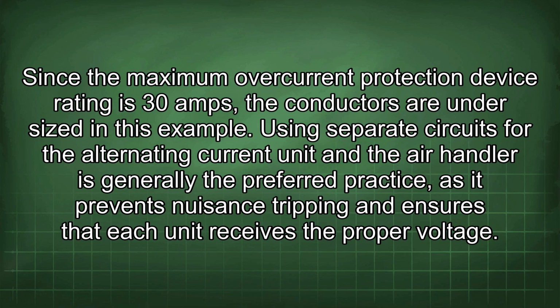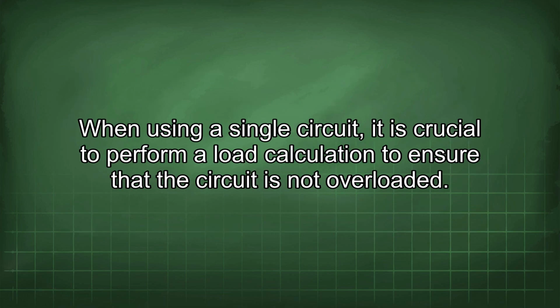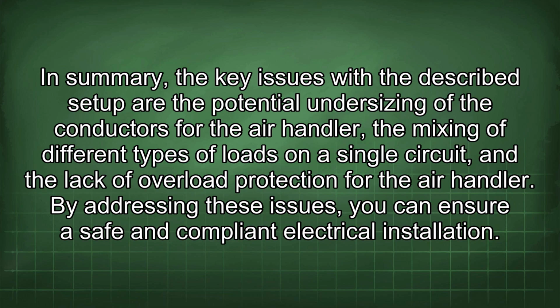Using separate circuits for the alternating current unit and the air handler is generally the preferred practice, as it prevents nuisance tripping and ensures that each unit receives the proper voltage. When using a single circuit, it is crucial to perform a load calculation to ensure that the circuit is not overloaded. In summary, the key issues with the described setup are the potential undersizing of the conductors for the air handler, the mixing of different types of loads on a single circuit, and the lack of overload protection for the air handler. By addressing these issues, you can ensure a safe and compliant electrical installation.